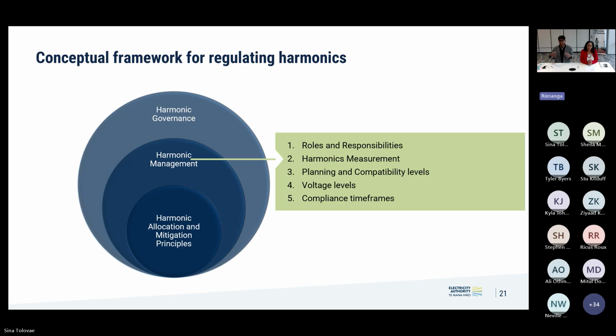That's why we're trying to keep this at a very high level: what's available in New Zealand, what's being done. Elsewhere, here in New Zealand we can measure up to 2500 hertz, but now because of inverter-based systems, some utilities overseas have gone up to 5000 hertz, because these solar farms have issues at more than 4000 hertz.